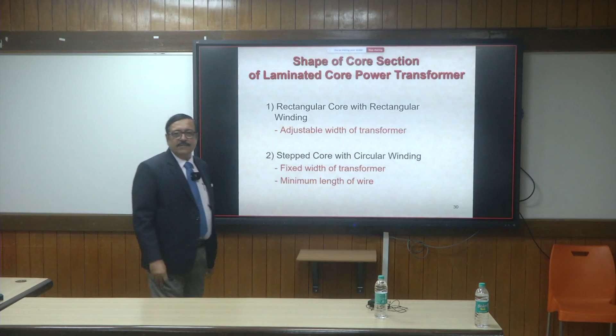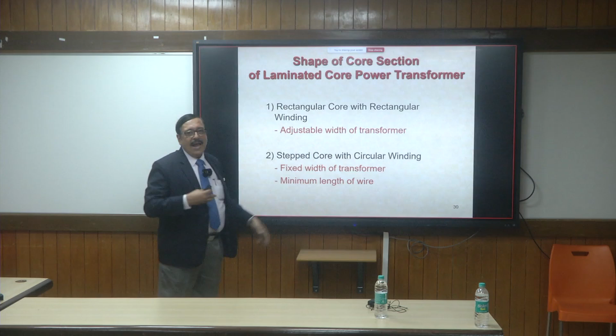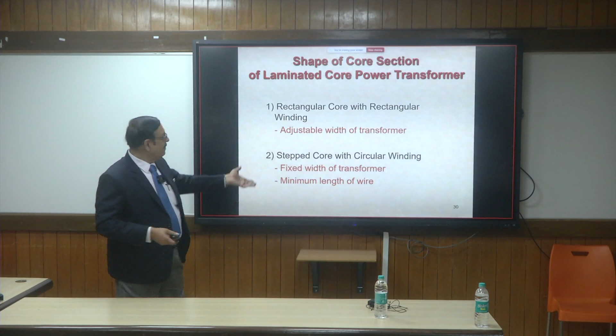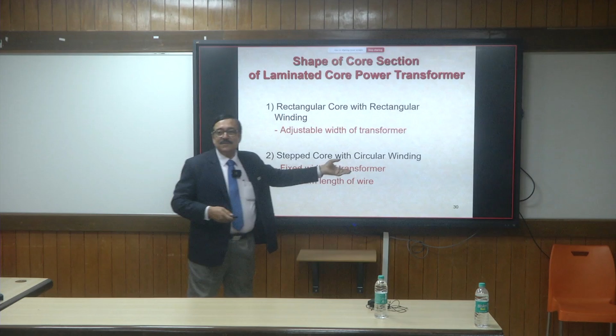So therefore, most of the equipment type transformers are made with rectangular cores, but if that restriction is not given, then we'll try to go in for a circular core, stepped core with circular winding. Why? Because the mean length of one turn in circular winding is always less than what you get for a rectangle of the same cross-sectional area. You can just work out for yourself. You take the same area of one circle and the same area of a square and try to find out the perimeter length. You will find the minimum perimeter will be for a circle. So we have less copper. Less copper means less losses, less temperature generation. Everything is beneficial.